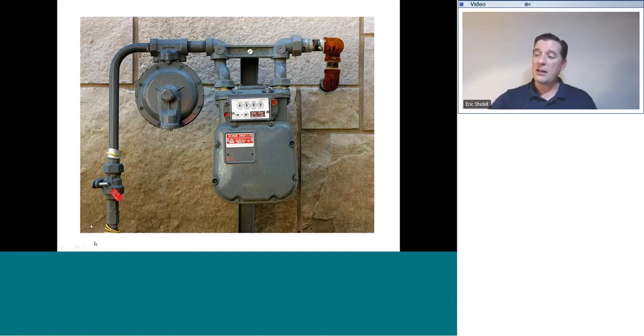A couple of things to pay attention to. That gas comes in on the left from the street, and the first thing that it runs into is a pressure regulator. This donut-shaped looking thing here is our natural gas pressure regulator. Now, the pressure that is in this line can vary widely from location to location. Where I live, the pressure that's in this line in some parts of town can be higher than 100 PSI.